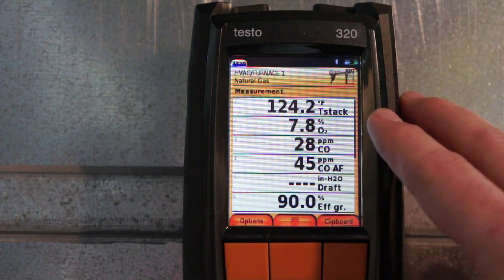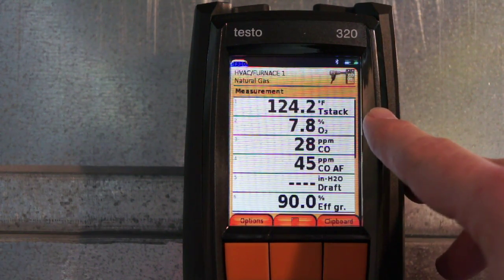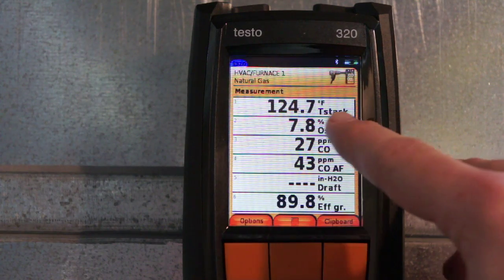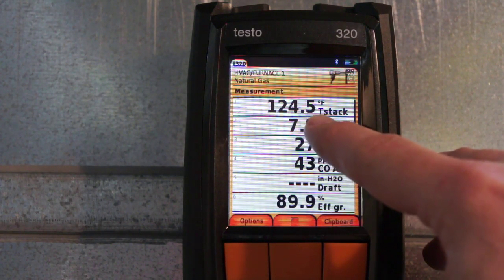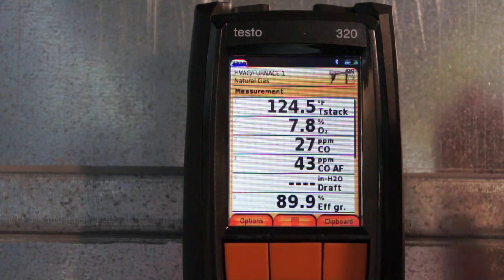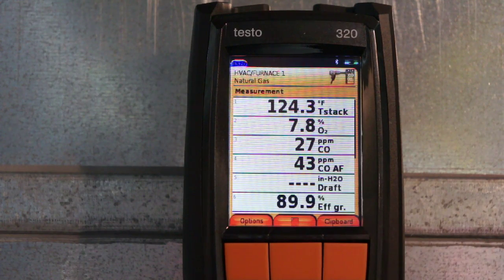Now, you can see here, my stack temperature is running at 124. And you can see it's bouncing around between 0.3, 0.7, 0.5. This is a stable stack temperature. This is the point at which we consider the furnace at steady state. And this is where we're going to start actually looking at our combustion and seeing how things are operating and making sure that other things are not going out of kilter.